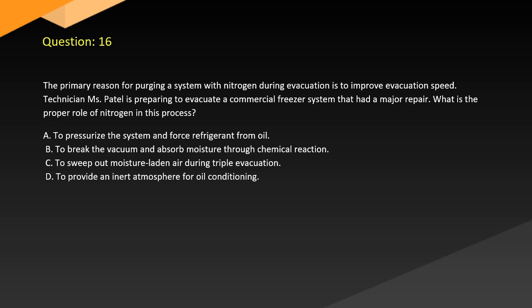Question 16. The primary reason for purging a system with nitrogen during evacuation is to improve evacuation speed. Technician Ms. Patel is preparing to evacuate a commercial freezer system that had a major repair. What is the proper role of nitrogen in this process? A. To pressurize the system and force refrigerant from oil. B. To break the vacuum and absorb moisture through chemical reaction. C. To sweep out moisture-laden air during triple evacuation. D. To provide an inert atmosphere for oil conditioning.